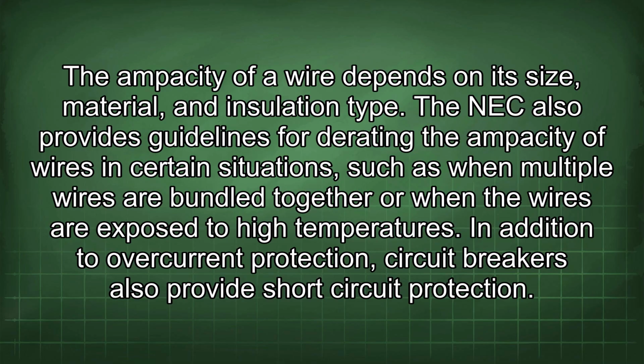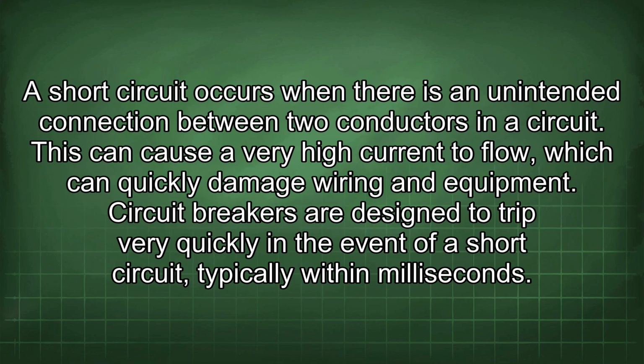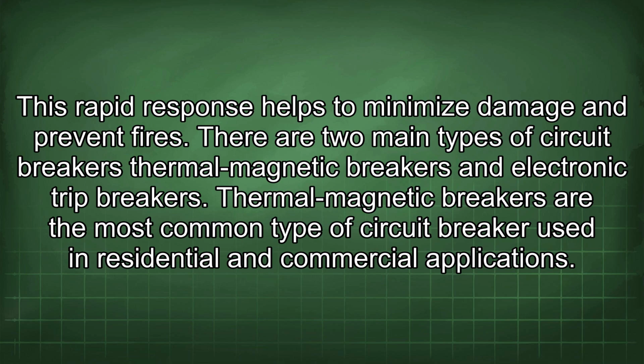In addition to overcurrent protection, circuit breakers also provide short circuit protection. A short circuit occurs when there is an unintended connection between two conductors in a circuit. This can cause a very high current to flow, which can quickly damage wiring and equipment. Circuit breakers are designed to trip very quickly in the event of a short circuit, typically within milliseconds. This rapid response helps to minimize damage and prevent fires.